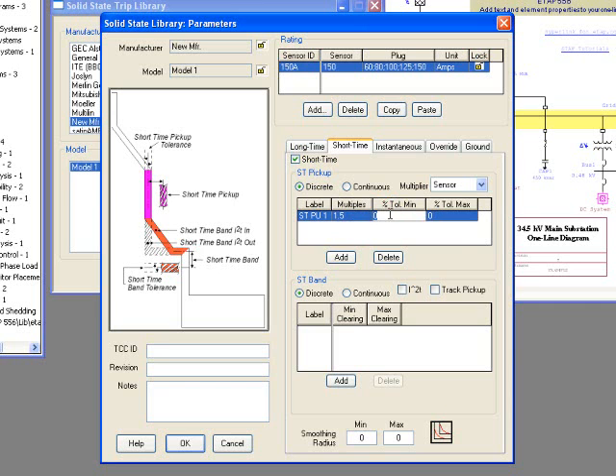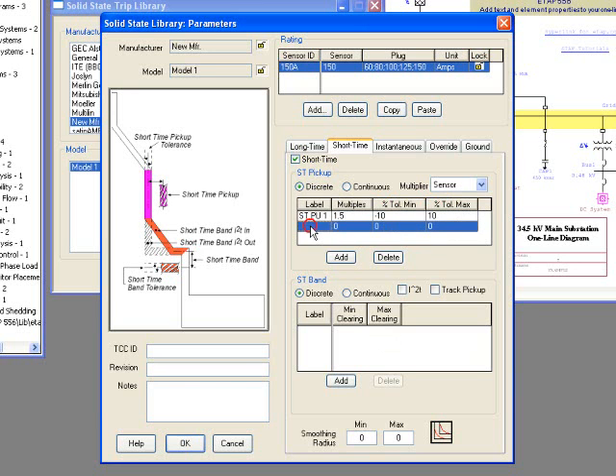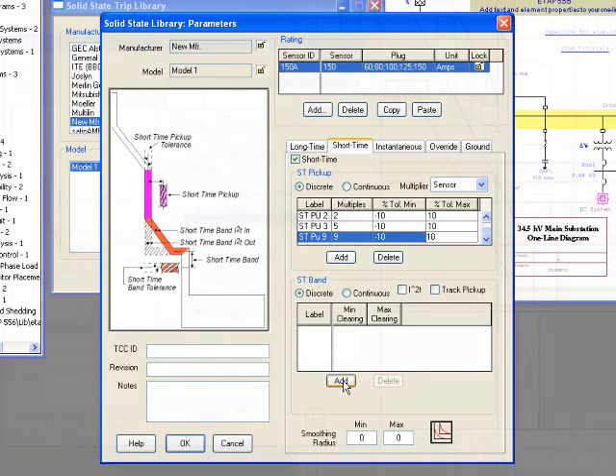Put the label for Short Time the same as the one for Long Time. Specify a multiplier for that specific Short Time pickup. Specify the tolerance percentage for minimum and maximum. Keep in mind your percent tolerance for minimum. You need to use the minus sign to get to the negative value.